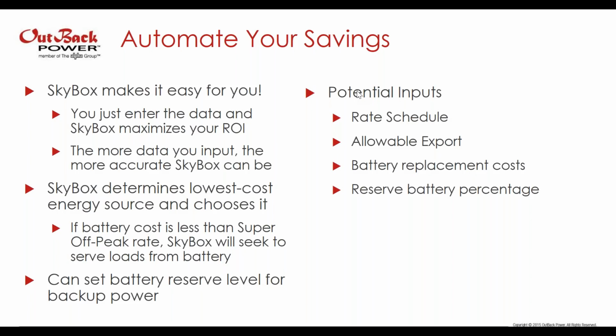So as the installer, there are 4 things that you would need to enter when doing the battery configuration. Your customer's rate schedule, and whether or not it's allowable to export power back to the grid at that particular location. The third thing would be your battery replacement cost. So that's you as the installer, what it would cost you to, at the end of the battery's lifetime, roll back and replace that battery. And then finally, the fourth thing is how much of the battery the homeowner wants to leave as a reserve percentage in case of outage.